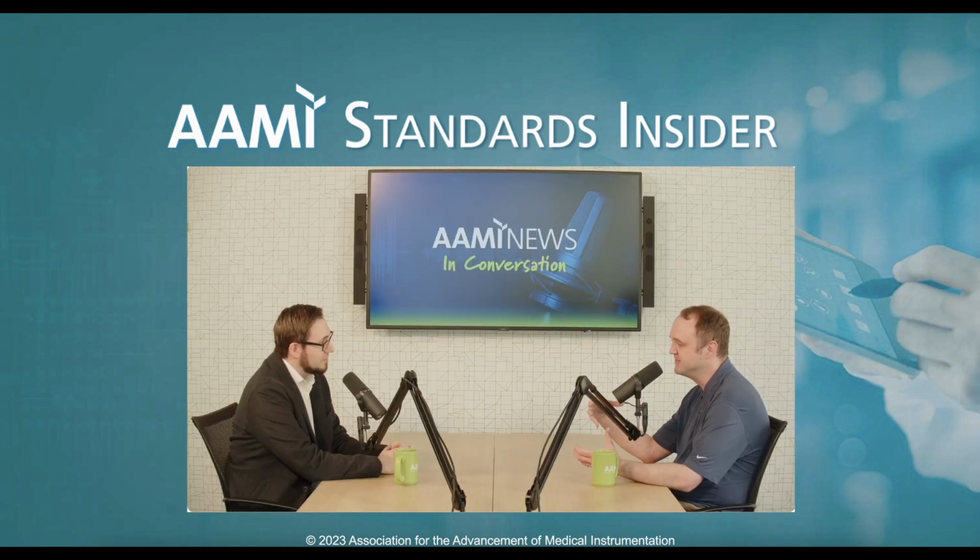And I can maybe just talk a little bit about the history. I believe this is the fourth revision of this TIR. It was first conceived in the late 90s, I believe 1997 was the first revision. And it started off as just relating to radiation compatibility. Actually started off as part of the radiation working group here at AAMI, where they put together a lot of information specific to compatibility of materials with radiation, as well as the aging material that went in there.